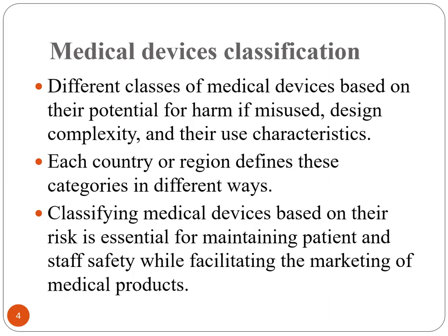medical products. Here we will depend on the classification based on hazard, the hazard of a misuse of a medical device. What is the hazard to the patient? They are classified as class 1, which has less potential to harm the patient or the user; class 2, intermediate; and class 3, which has a high potential to harm the patient or the user if they are used by mistake or misused.